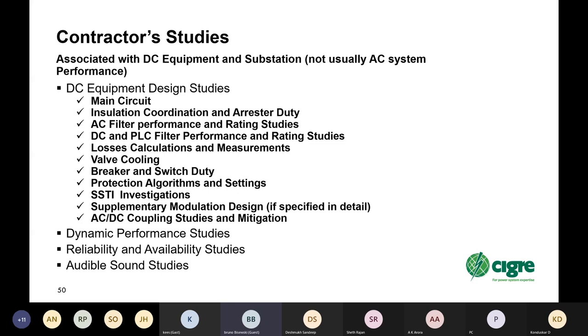So basically, contractor studies include DC main circuit design studies, insulation coordination, AC filter performance and rating, DC and PLC filter performance and rating, loss calculations and loss measurements later, valve cooling system design study, breaker and switch duty design studies, protection algorithms and settings, SSTI investigations, supplementary modulation design, if you've specified them in detail, as we previously noted, and AC and DC coupling studies and mitigation. This could also be an owner study, and typically is an owner study, but if you haven't done it, it can be done as a part of the supplier studies.